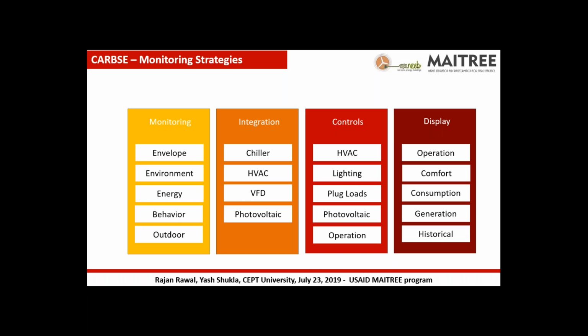In the third division, we were talking about control. So once we monitor and integrate, we can start controlling the different aspects of the building: lighting, plug loads, HVAC systems, even looking at whether the photovoltaics need to be switched off in a certain portion of the day, or whether we have to bypass some of the energy generated and divert it towards the campus as opposed to the building. So those are the aspects where the controls get into the picture.